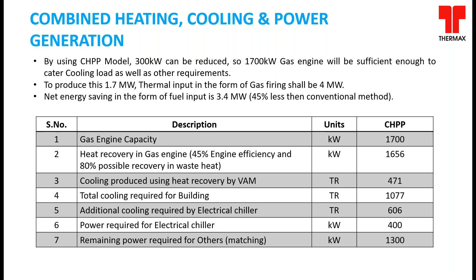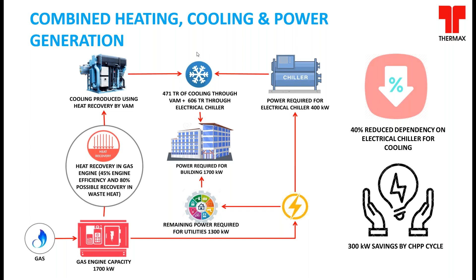So because of this, you can see in the new scenario the overall installed capacity is lower. We run an engine to cater to the power requirement of the building, and we generate cooling free of cost. We also reduce the size of the electrical chiller as well as the power required by it. So the total savings for the user are 300 kilowatts of power savings and a 40% reduction in dependency on the electrical chiller.